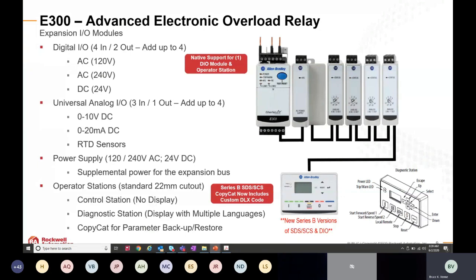And then down at the right-hand side, another nice element for the E300 is what's referred to as either a control station or a diagnostic station. The control station just has a series of buttons and a reset that you can use to control the device, whereas the diagnostic station adds a small LCD display, so you can scroll through some of the parameters and see how the E300 is operating and what it's monitoring and things of that nature.